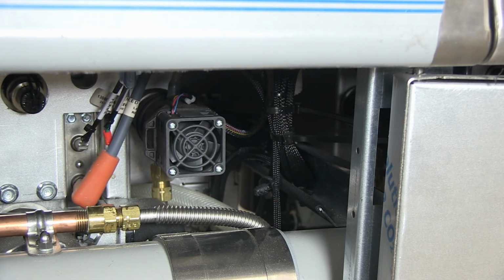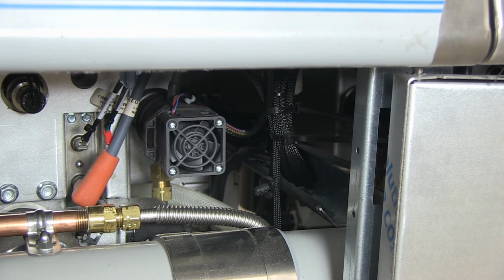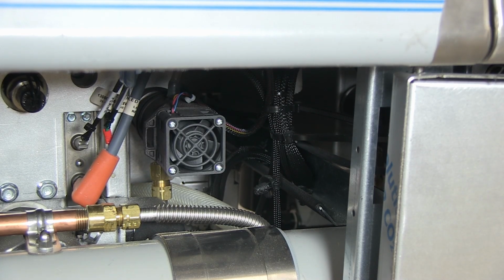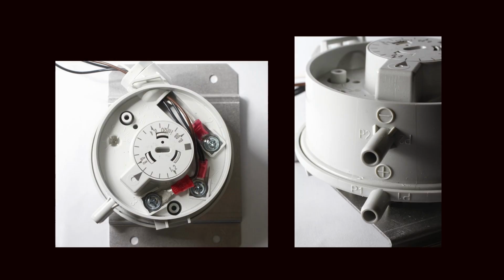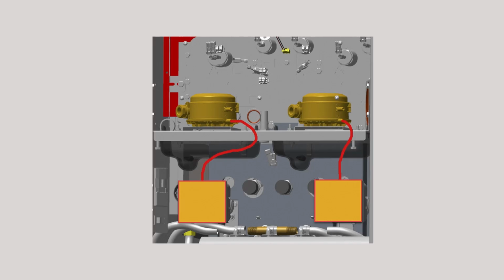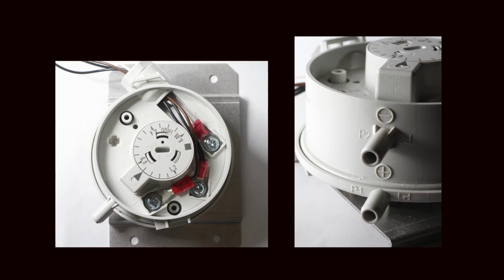As a safety, the 24 volts for the spark modules is in series with the pressure switch. No pressure, no voltage for spark or the gas valve. The voltage can be measured at the switch when the fryer is calling for heat. The hose connecting the pressure switch to the blower can be seen in this illustration. A switch is shown here, removed from the fryer for clarity.